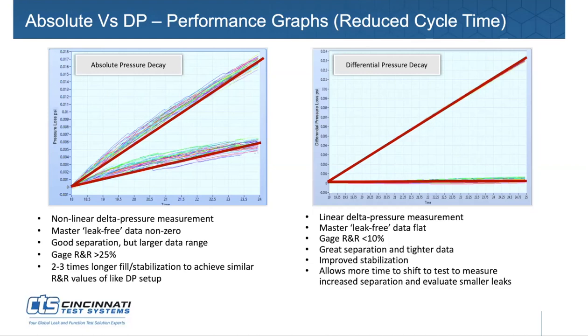It's very easy to take a differential pressure decay system and cap off the reference side to get a very repeatable test. 90% of our customers test that way. As you get into some possibly lower leak rates, comparing some very precise measurements, then you might have a volume very representative of the part volume. The problem with having a reference volume is there's another part in the system now that could leak. There's another part in the system that could change temperature based on external effects. So that's something to keep in mind when you use specialty testing like this.